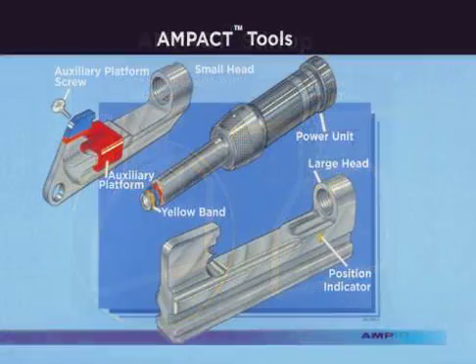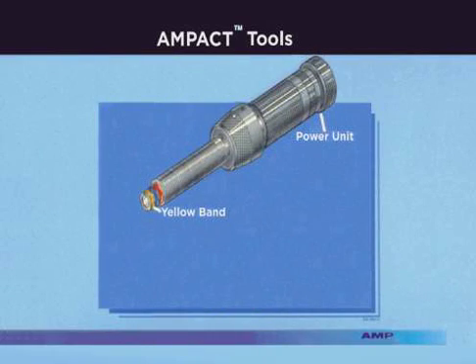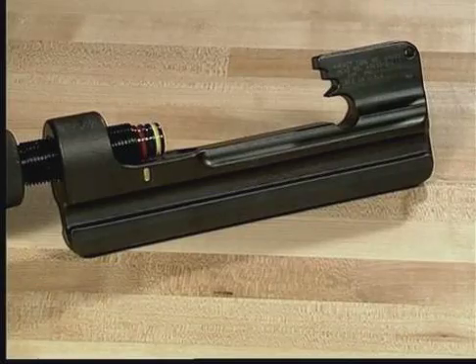The AMPACT application tool consists of two components: the head and power unit. Two types of heads are available, small and large. The small head is used to apply small red-coated TAPs and medium blue-coated TAPs, as well as the copper and Type 2 TAPs. The large head is used to apply the large yellow-coated TAPs. Both heads are interchangeable with the power unit, however, they are not available separately.